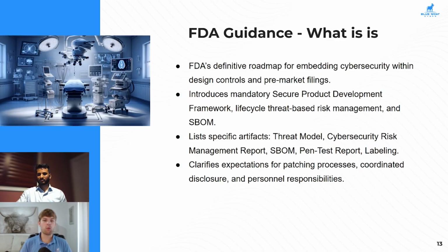We're looking at a risk-based approach to handling risk management. So scaling levels of risk depending on scaling levels of device complexity and involvement, talking about generating that SBOM, maintaining that SBOM, what we're doing as far as our testing procedures. And the FDA guidance also talks about all of the accompanying standards that are important for a specific procedure or a specific process. This is where we see references to NIST 800-115. This is where we see references to IEC 62304. So the FDA guidance is talking about all of these other standards and how they can interact in different ways to ensure that we have complete coverage about security for the device.